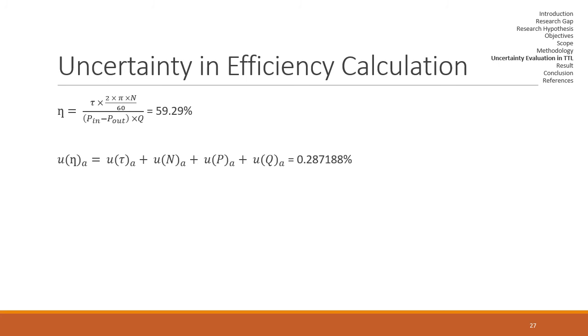The type A uncertainty for torque that we just calculated is denoted by U tau A. So for the combined type A uncertainty of efficiency, following the rules of uncertainty calculation, we need to add the type A uncertainty of torque, RPM, pressure, and flow, which we get 0.287188%.